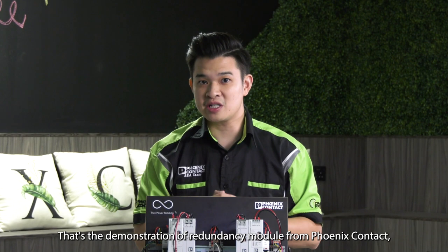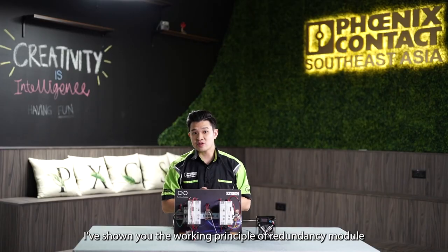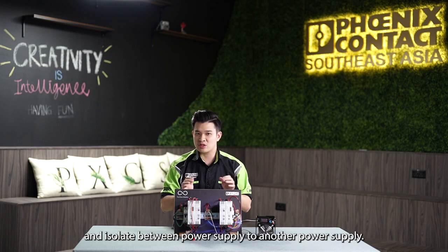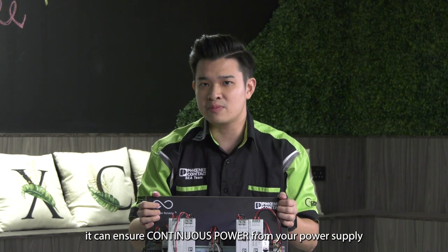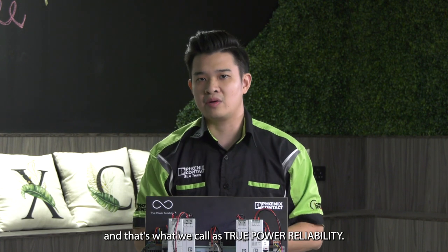That's the demonstration of the redundancy module from Phoenix Contact — our QUINT4-S-ORING. I've shown you the working principle of the redundancy module and how it can prevent backflow of current and isolate between one power supply and another. With the redundancy module, it can ensure continuous power from your power supply, and that's what we call true power reliability. Thank you.